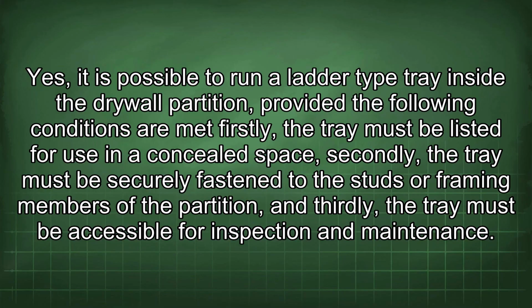Yes, it is possible to run a ladder-type tray inside the drywall partition, provided the following conditions are met. Firstly, the tray must be listed for use at a concealed space. Secondly, the tray must be securely fastened to the studs or framing members of the partition. And thirdly, the tray must be accessible for inspection and maintenance.